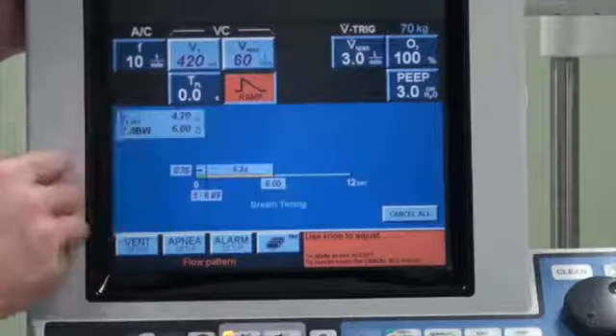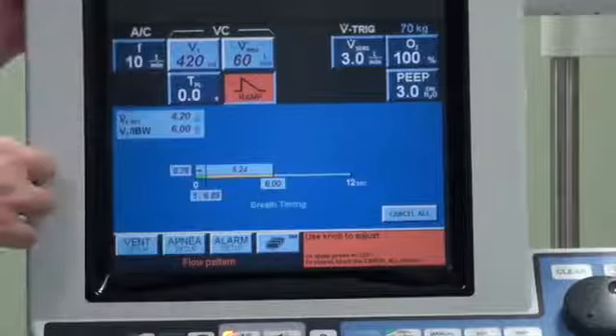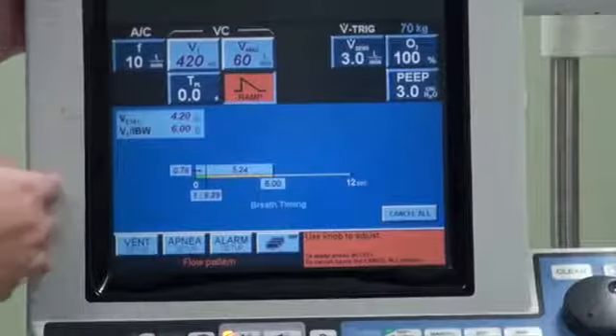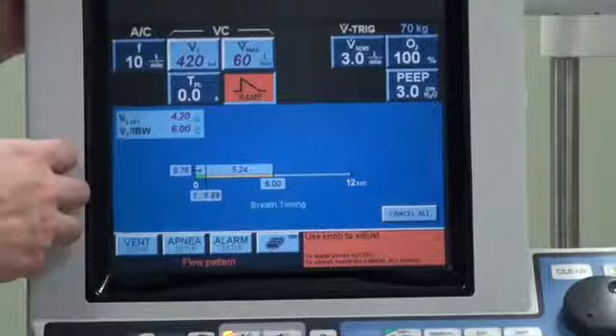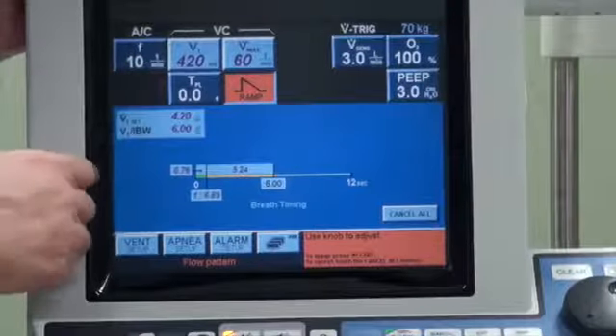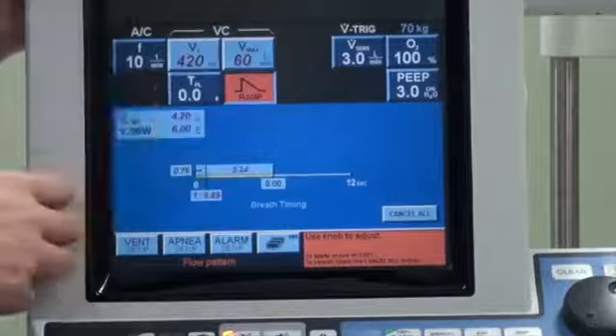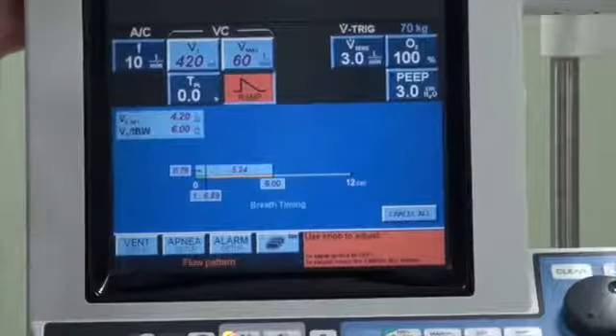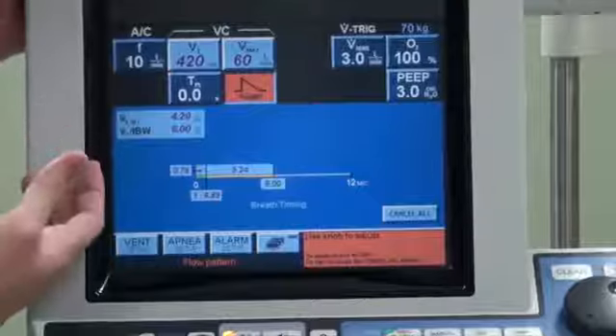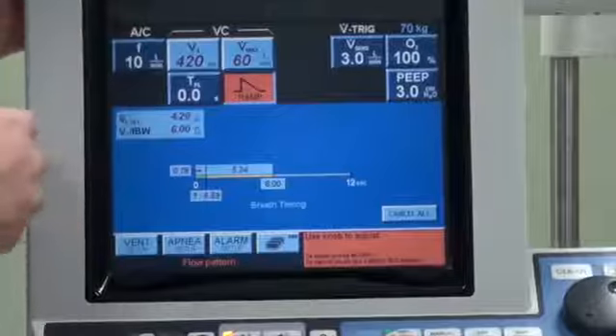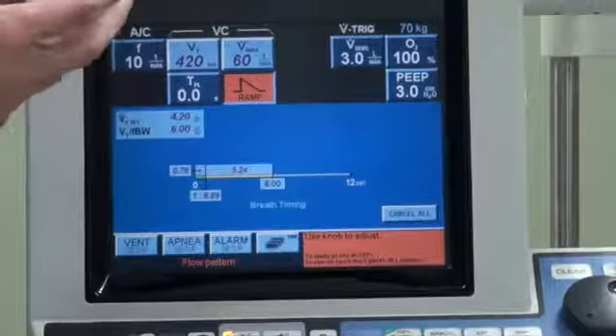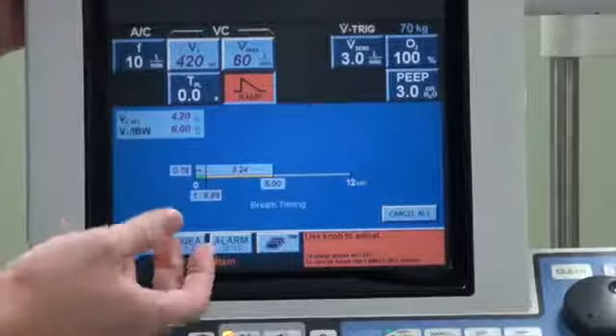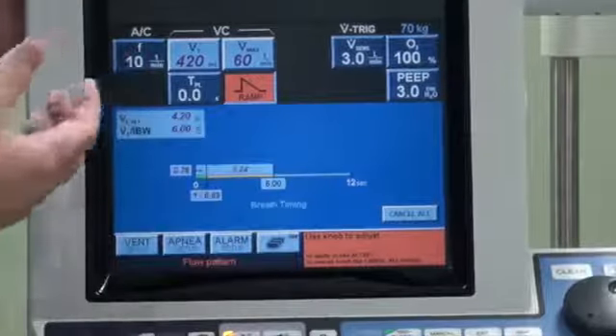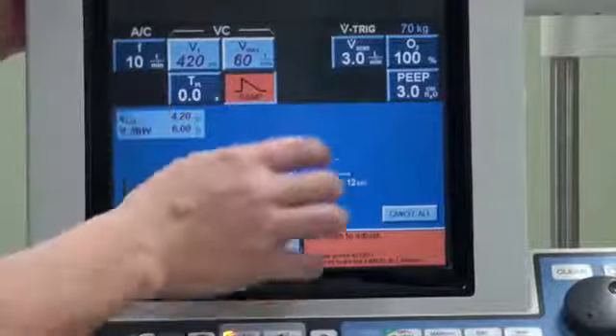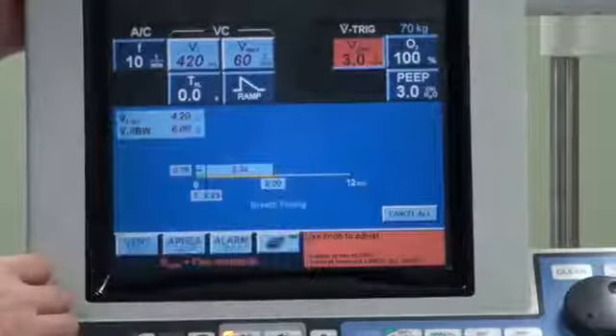Next would be the flow trigger, which tells the ventilator whether the patient is trying to initiate a breath, and it can be determined by either pressure or flow. So here, the higher the number, the less easy it is for the ventilator to detect the patient's attempt to generate a breath. The lower the flow, the higher the sensitivity. So the ventilator will very easily pick up a patient's effort. A typical flow trigger we'll put at either 2 or 3. So we will just keep the setting as it is now.